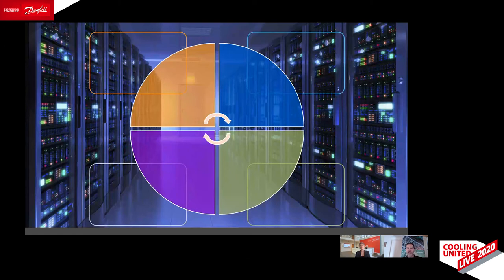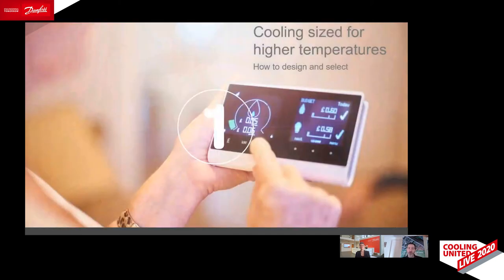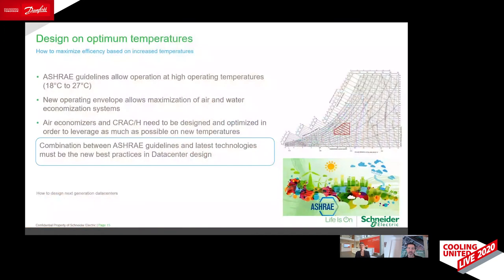We rate these and we select the top four in this list. The list is very, very long, but we try to select the top four. The number one, in our opinion, is certainly how you design the data center. It is not a very recent evolution that temperatures in the data center are higher than in the past. But now it is a fact that the majority of data centers are, or should be, designed at a discharge temperature of 25, 26 or 27 degrees Celsius.